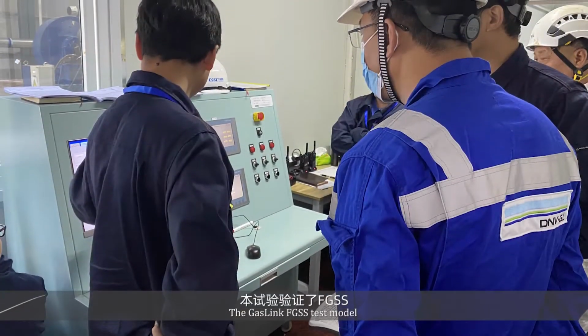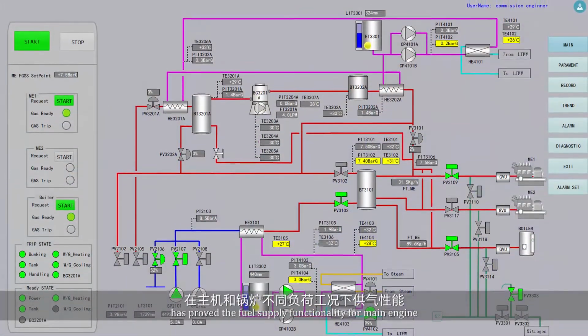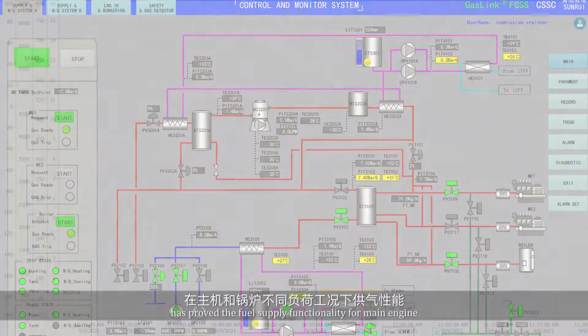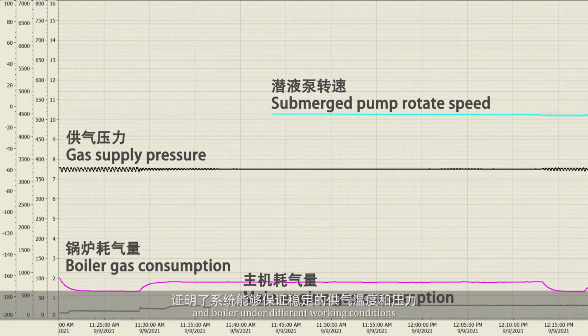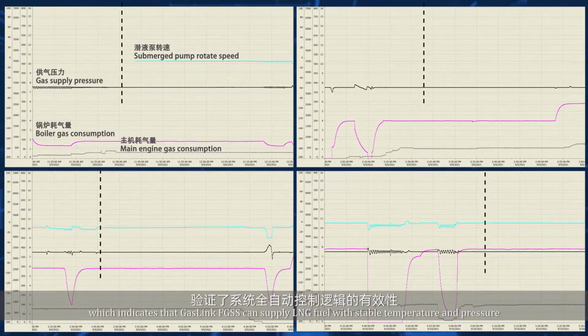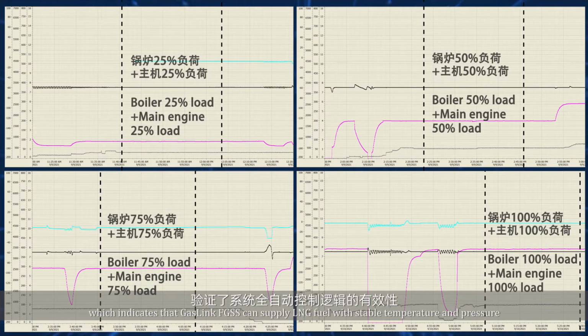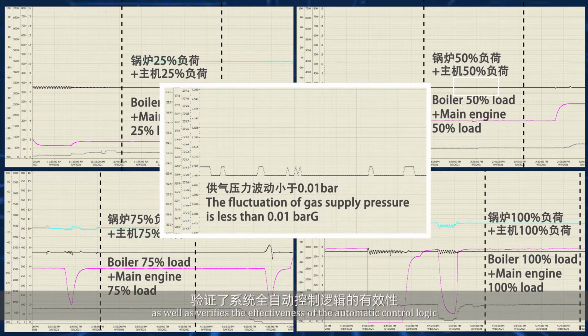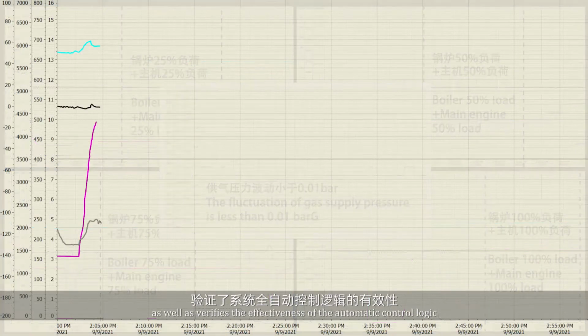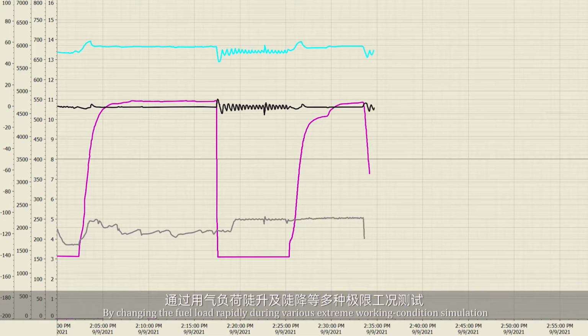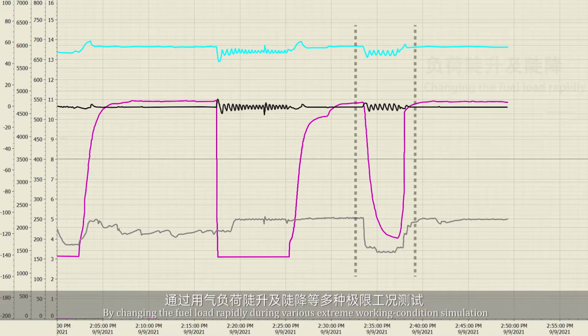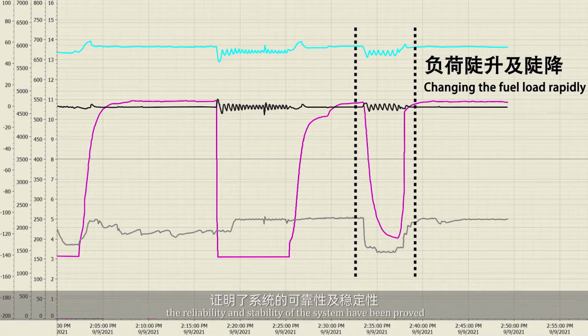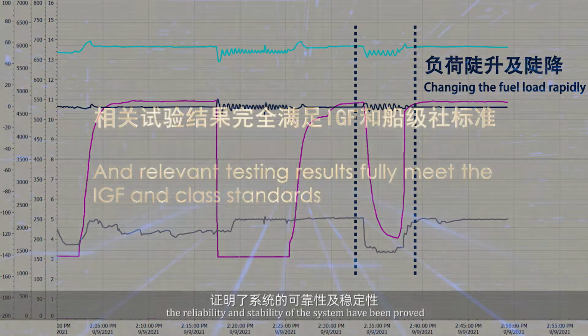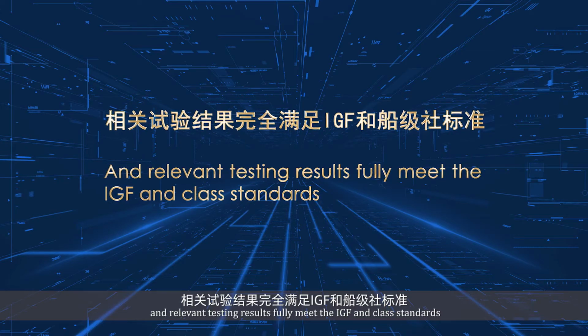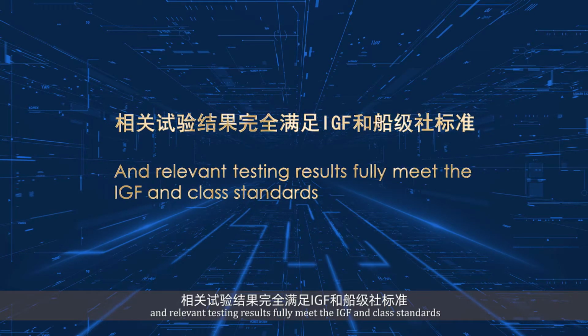The Gaslink FGSS test model has proved the fuel supply functionality for main engine and boiler under different working conditions, which indicates that Gaslink FGSS can supply LNG fuel with stable temperature and pressure, as well as verifies the effectiveness of the automatic control logic. By changing the fuel load rapidly during various extreme working condition simulations, the reliability and stability of the system have been proved, and relevant testing results fully meet the IGF and class standards.